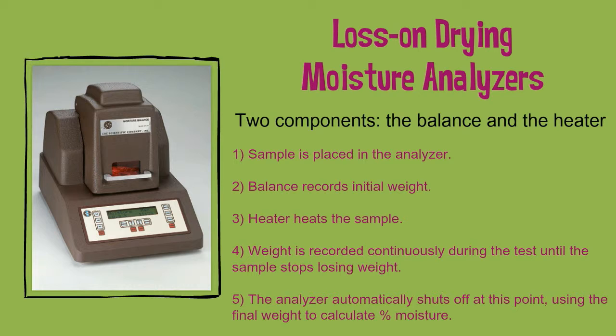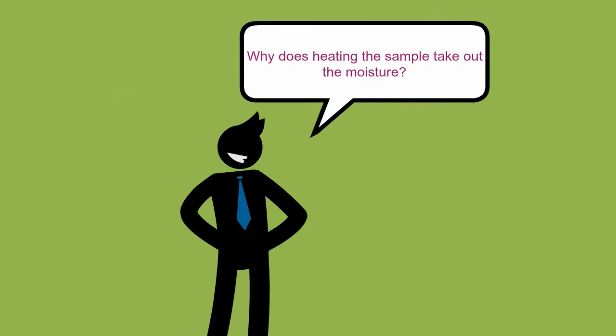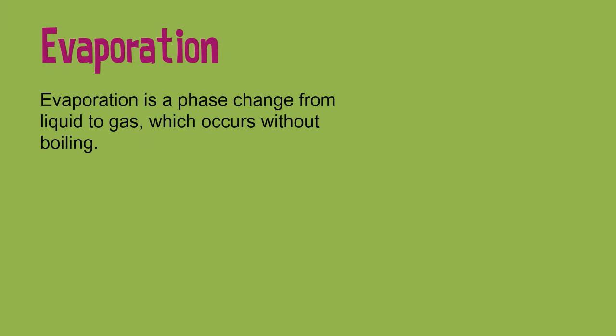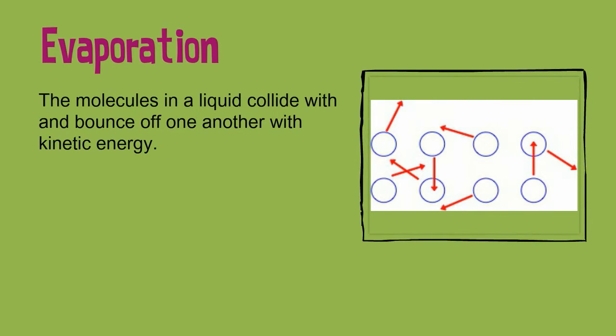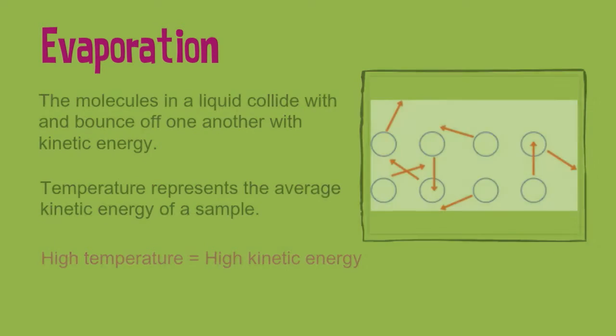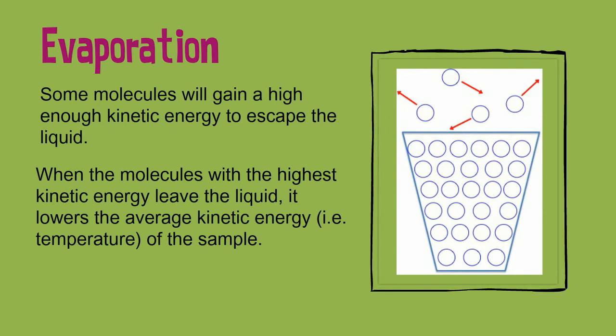In these instruments, the sample is placed in the analyzer where it is heated and automatically turned off when the test is finished, and the percent moisture is calculated. The process of LOD moisture analysis is made possible by the phenomenon of evaporation — the process of changing moisture from a liquid to a gas or vapor without boiling. This process happens when kinetic energy in the material causes the water molecules to bounce off each other and fly out of the test sample. The process is driven by heating the sample.